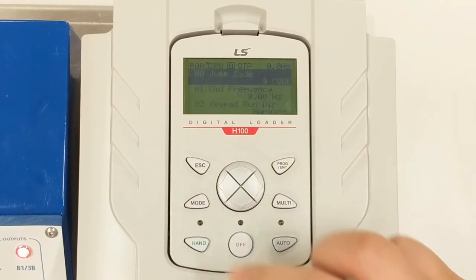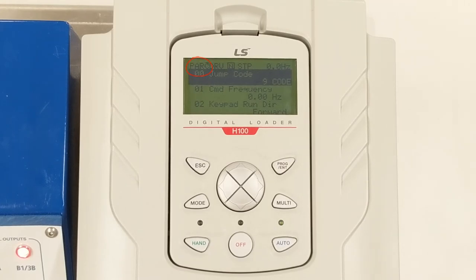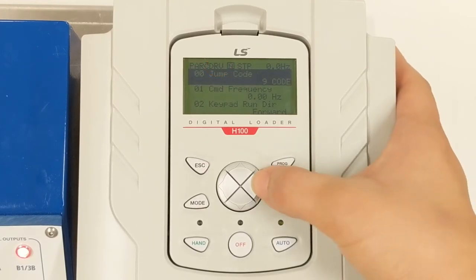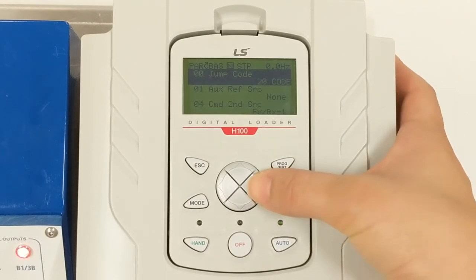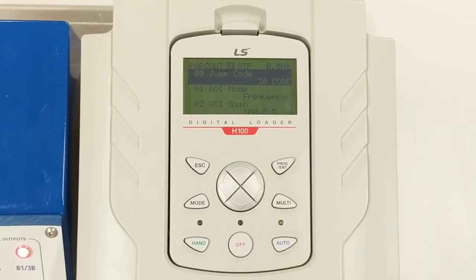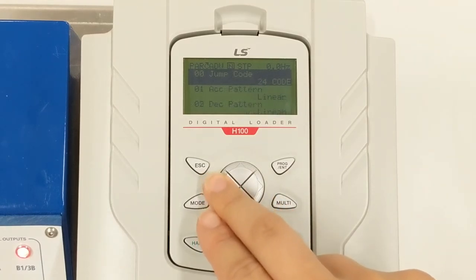Pressing the mode key will change the keypad's mode to the parameter display. We can see this because PAR is displayed in the top left corner. To the right of PAR is the parameter group. Here we see DRV. Pressing the right arrow, you will see a number of other groups: BAS, ADV, and others. These parameter groups are broken down into an easy-to-remember order. Most common parameters are set in the DRV and BAS group. For a full list of parameter groups and settings, refer to the full H100 user manual. Press the left or right arrows in the parameter mode to get back to the DRV group.